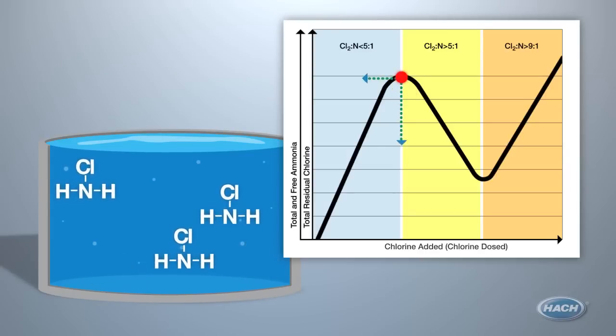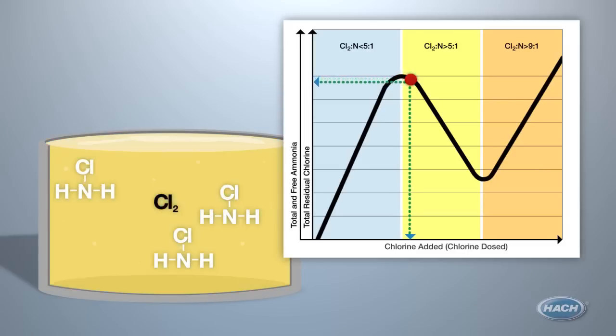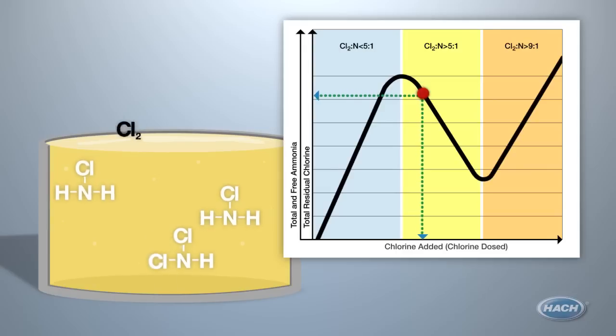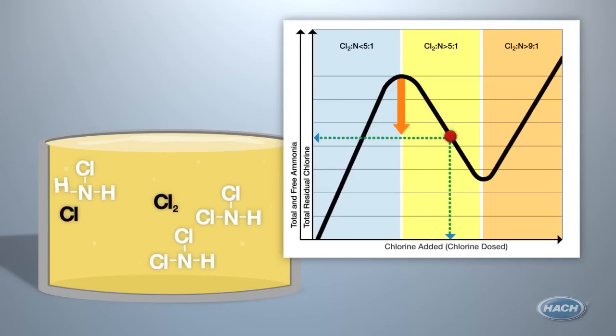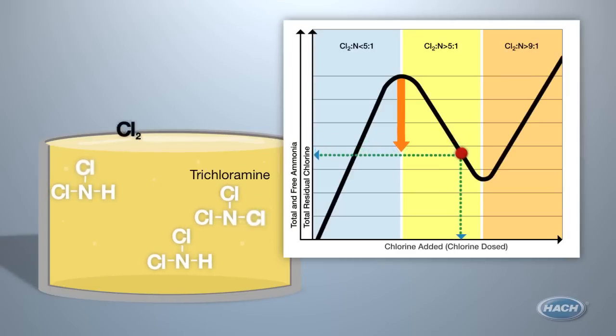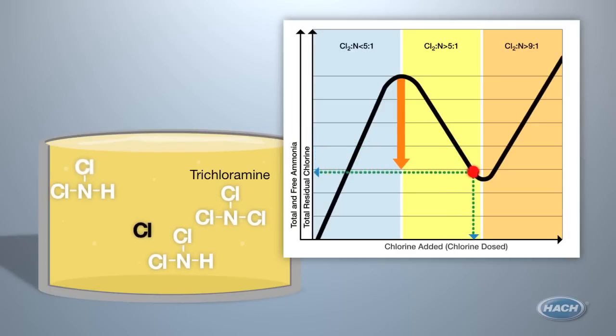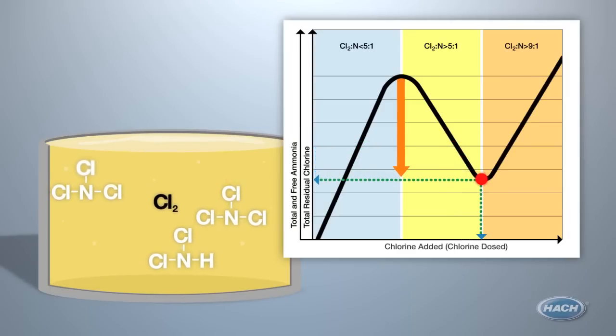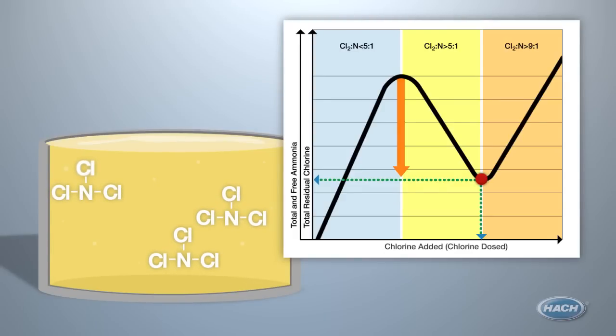If you continue to dose chlorine past this state, you begin to experience di- and finally trichloramination. These states are not ideal. It causes your chlorine residual to drop radically, although you are adding more chlorine. You will experience taste and odor issues when you are in this zone, and your disinfecting power is drastically cut.